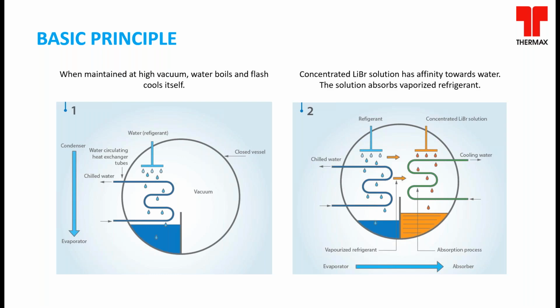So the second part of the slide, you can see there is a chamber adjacent to the evaporator, which is called the absorber. This absorber's duty is to absorb the refrigerant vapor which is getting generated in the evaporator, thereby maintaining the constant vacuum or constant pressure inside the chiller. This is achieved by spraying the concentrated lithium bromide solution in the absorber section. Like any other salt solution, lithium bromide salt also has a very high hygroscopic property. Hygroscopic meaning it has an affinity, or a capability, to absorb water vapor. When this water vapor is getting absorbed, there is a heat of dilution which gets generated, which is dissipated to the cooling tower water circulating through the absorber tubes.